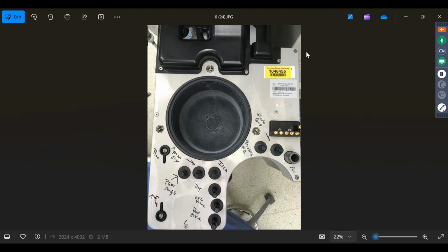This is a nice little thing. It's got all the names of all the ports on the VGC, or ventilator gas controller, the fresh gas port. Now, if you want to check a vaporizer, you can make yourself a little rig that connects with a Y that connects the fresh gas to the waste port right next to it, and then has a luer T at the top, and you use a sample line to go into the anesthesia machine's gas analyzer, and you can check your vaporizer anesthetic concentrations that way.